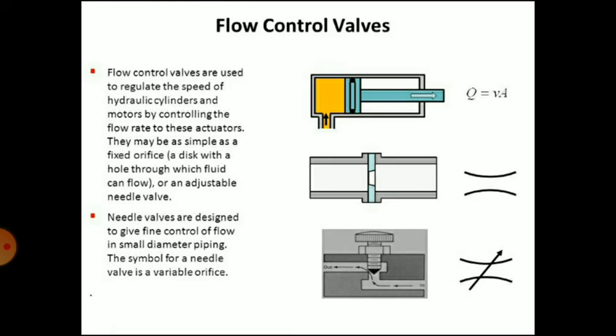Flow control valves are used to regulate the speed of hydraulic cylinders and motors by controlling the flow rate to these actuators. They may be as simple as a fixed orifice — a disc with a hole through which fluid can flow — or an adjustable needle valve. Needle valves are designed to give fine control of flow in small diameter piping. The symbol for the needle valve is a variable orifice.